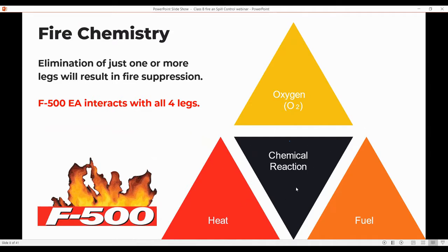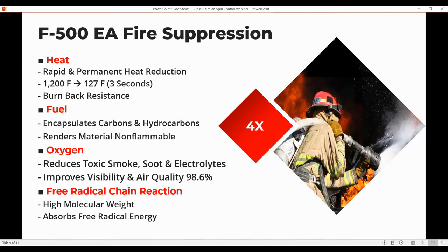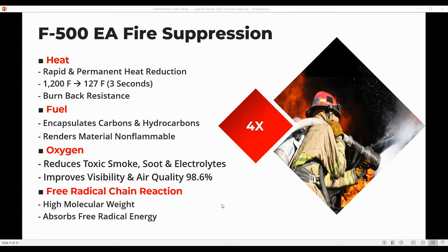With an encapsulating agent like F500, you get rapid and permanent heat reduction — removing the heat. You have the encapsulation of those fuels inside the spherical micelle, separating that fuel from the oxygen on a chemical molecular level. And testing done by Clemson University shows we can actually interrupt that free radical chain reaction as well. So we're working on all legs of the fire tetrahedron simultaneously as opposed to just one.